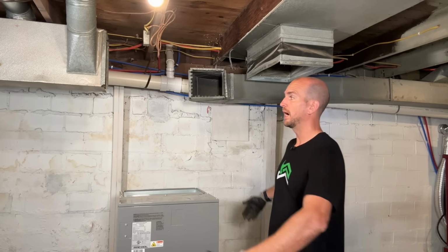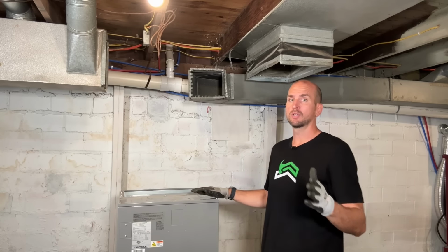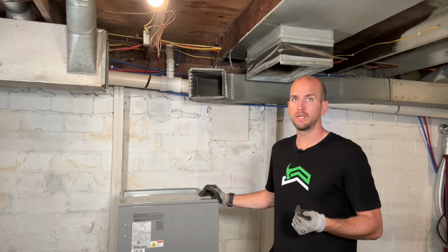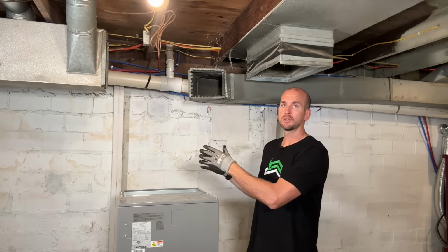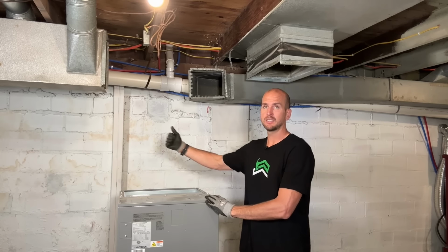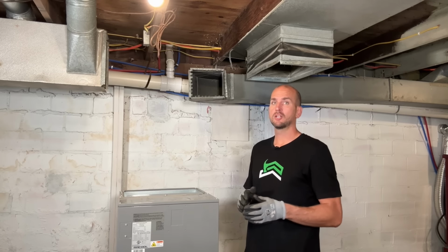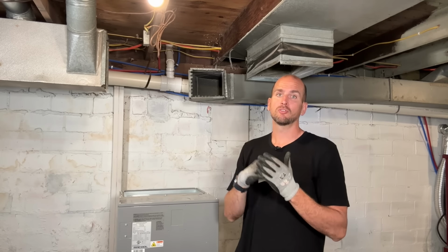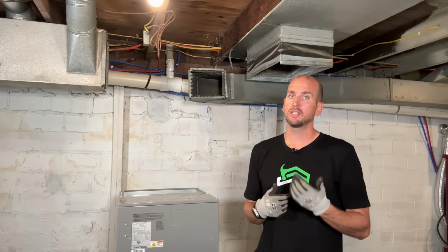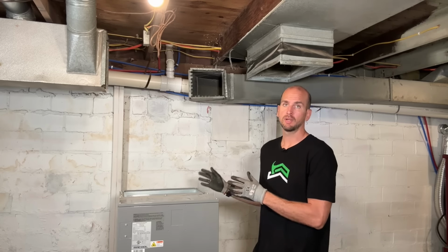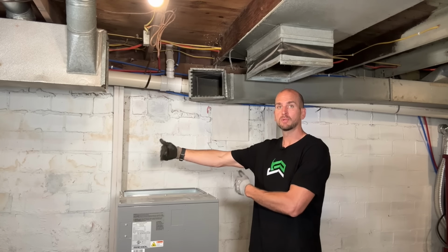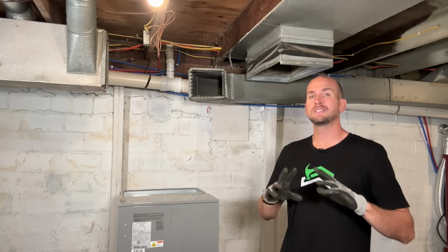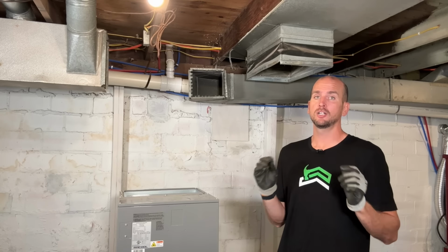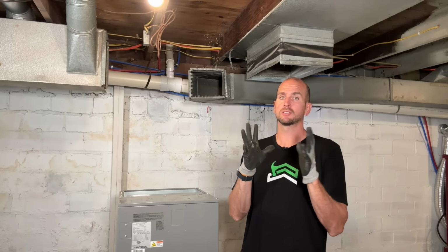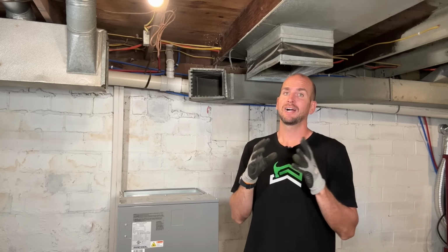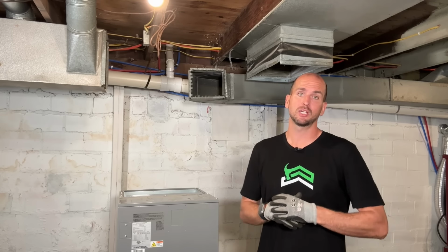Now I am in a wide open space here. If you are in the closet, you need to think through that as well. As you start to put your ductwork in place, you're gonna start to lose access to certain sides. So the way you're bending some of your lips, the way you're fastening it together, you have to think through that in terms of how much space you have, especially when you're dealing with a utility closet. And then don't forget, you'll be dealing with sheet metal and a ton of sharp edges, and it will cut you right open. So cut resistant gloves are highly recommended, and probably even some eye protection is not a bad idea.